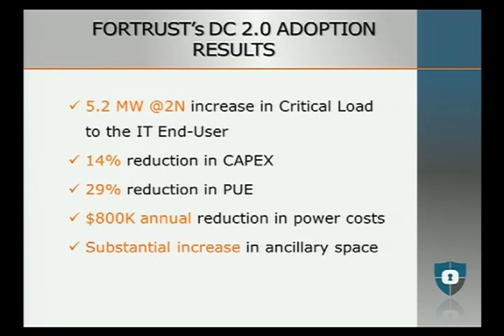Some of the results we've seen: in 2012, once we went to a more modular design and delivery of data center capacity, we achieved a 5.2 megawatt at 2N increase in critical load to the facility without ever moving a wall, without ever physically expanding the facility itself. We managed to get a 14% reduction in capital costs of construction, including soft costs, a 29% reduction in PUE, and we estimated we should save about $800,000 annually in power costs. As a byproduct, we had a substantial increase in ancillary space.